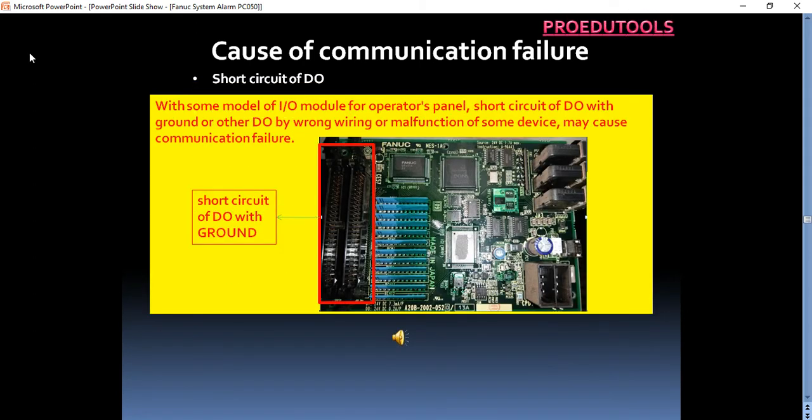Short circuit of DO. With some model of IO module for operator's panel, short circuit of DO with ground or other DO by wrong wiring or malfunction of some device may cause communication failure.